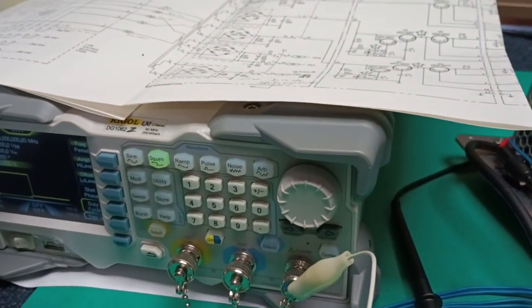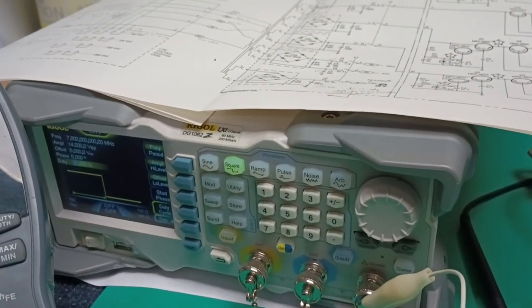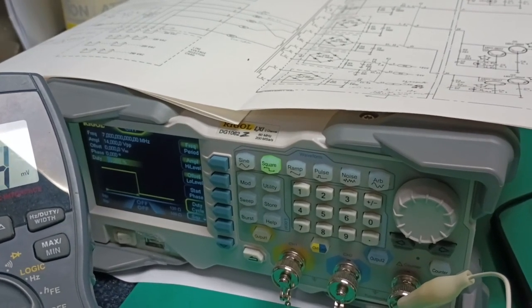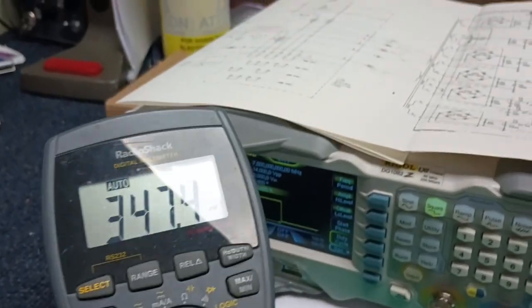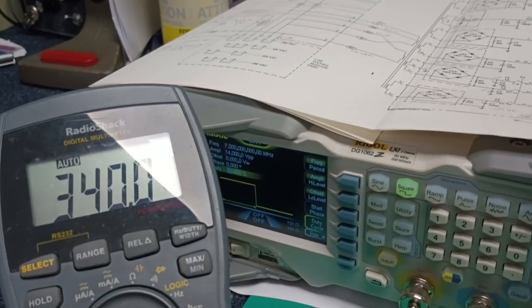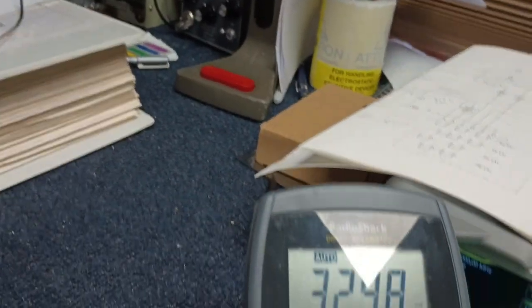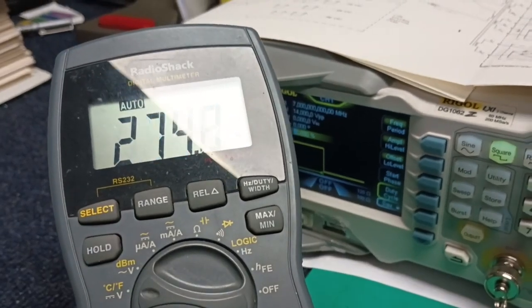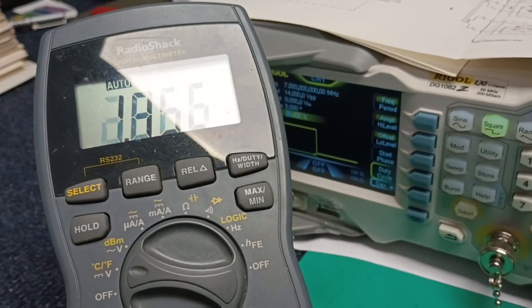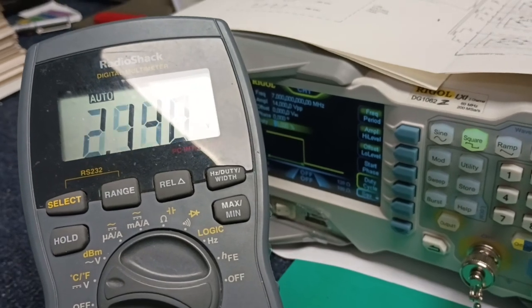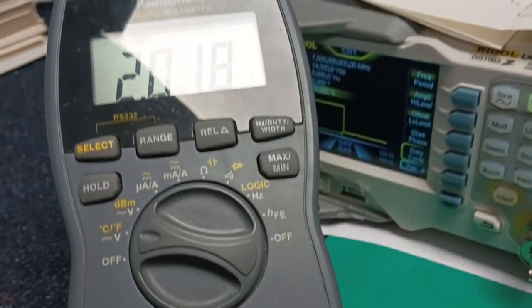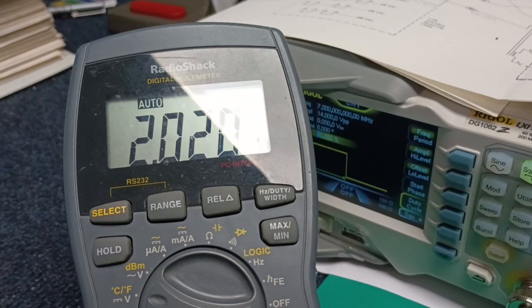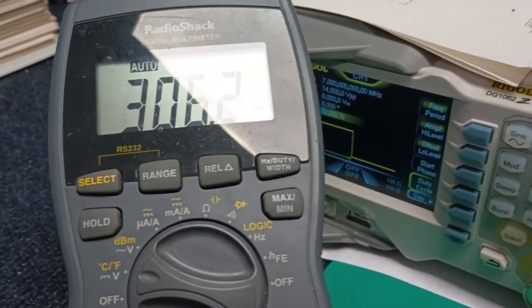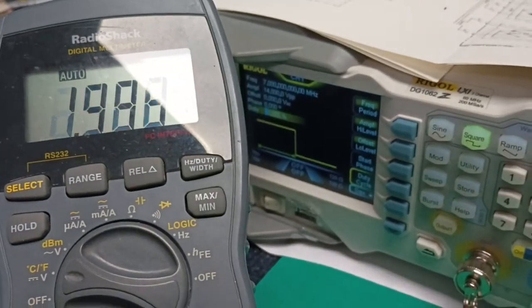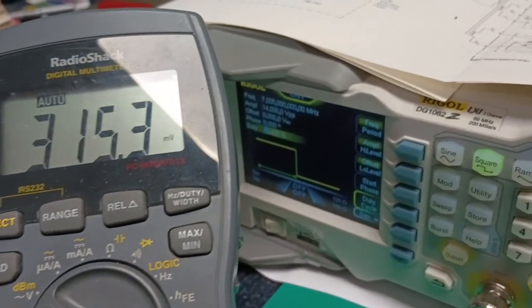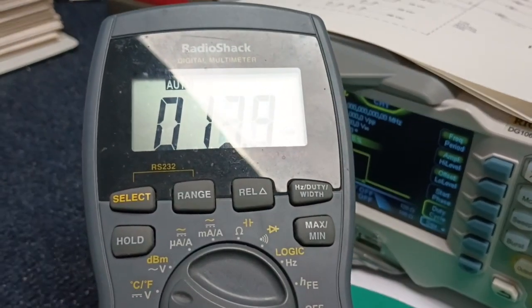So I'm going to take the voltmeter and touch plus, minus, and supposed ground and supposed neutral on each of these power supplies, so you can see in the meter what the results are. There is, on the plus 20 volt supply at the so-called earth terminal, a strange reading. And when a voltmeter is set on DC and we get a weird reading like that, it probably means there's an AC component. But notice there are anywhere from a couple of volts to a couple hundred millivolts. See the millivolt indicator on that supply.